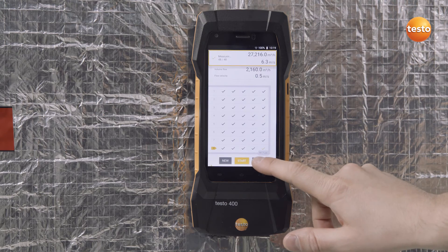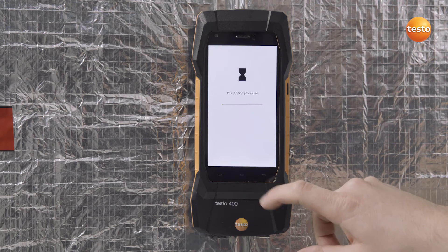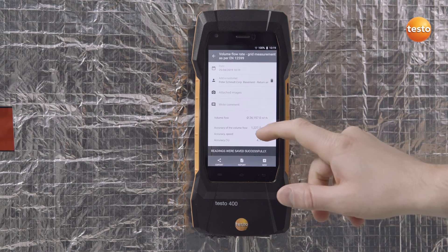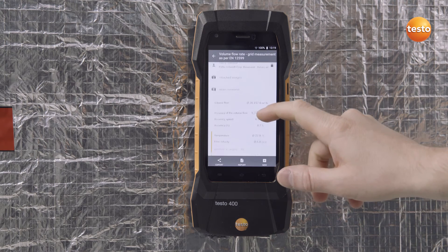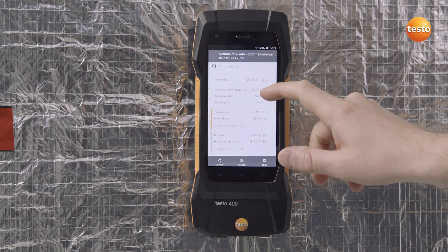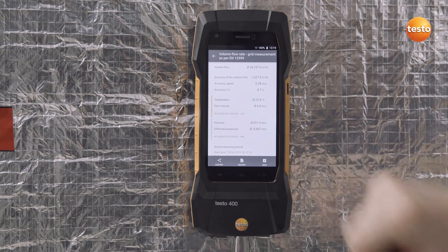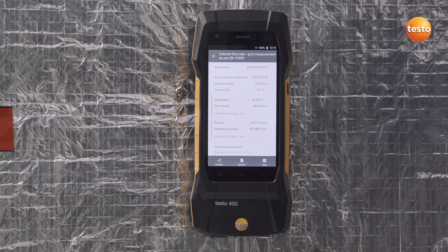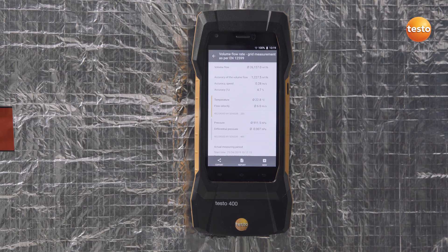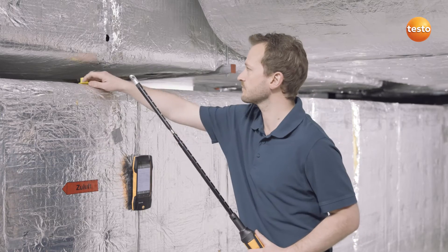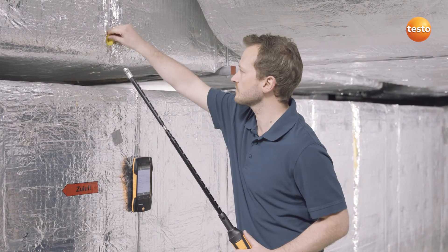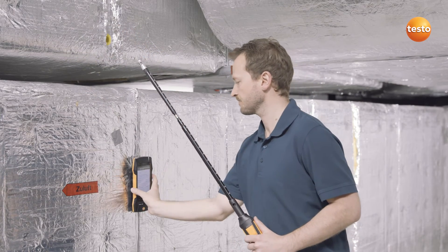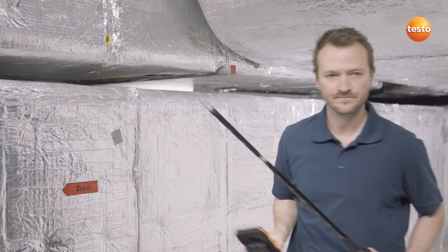Proceed this way for all further measurement points and insertion depths. Now save the measurement. The Testo 400 also shows you the accuracy readings in addition to the measurement results. We're finished with the duct and carry on to the outlet measurement.